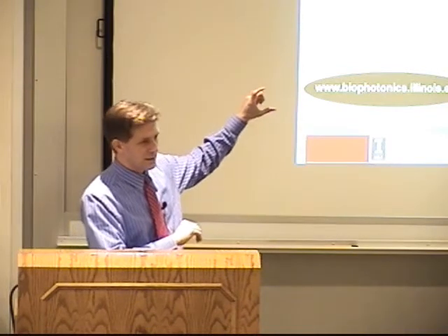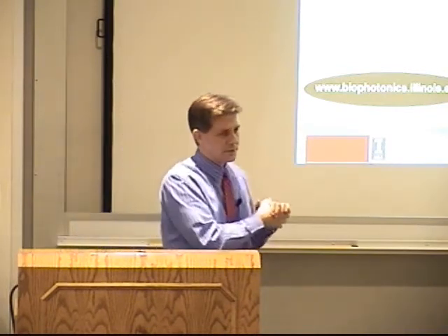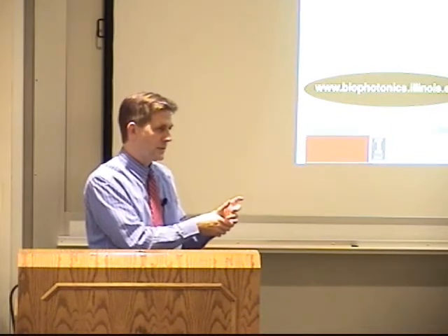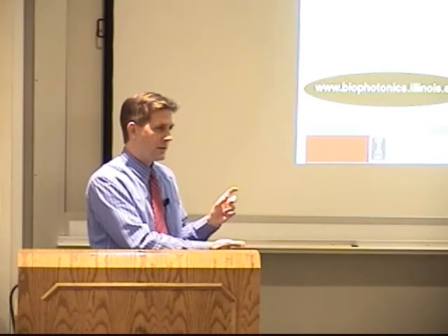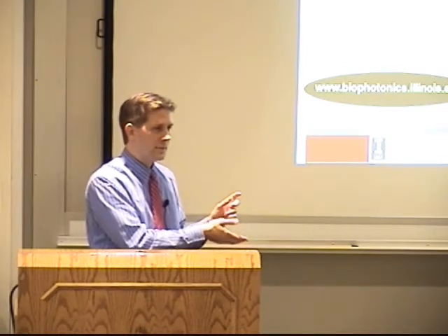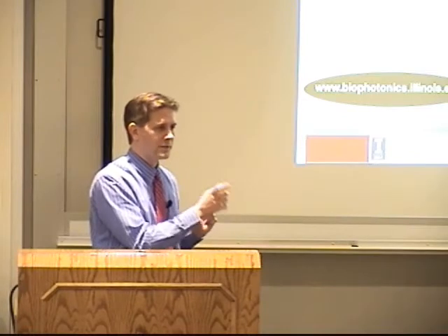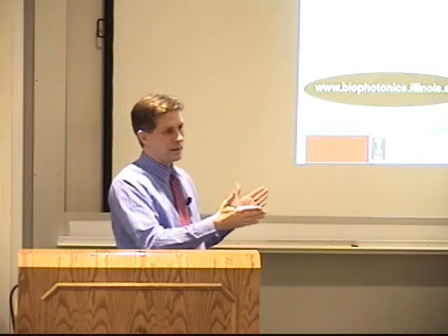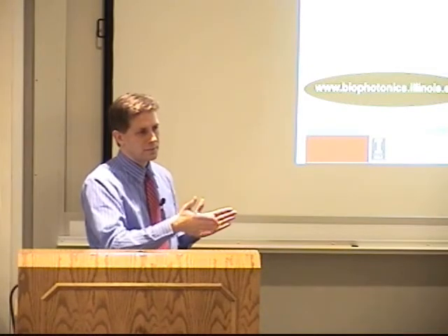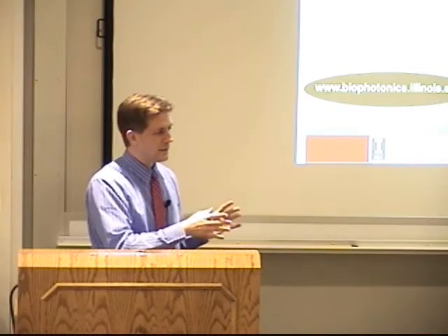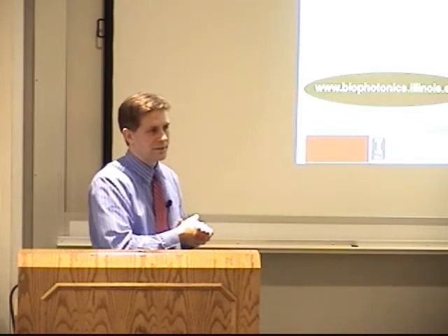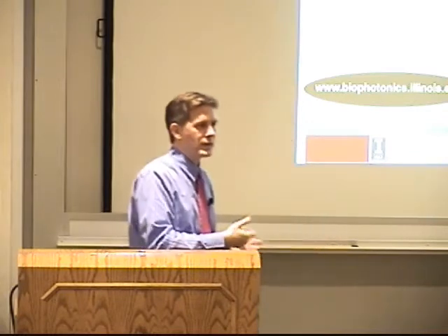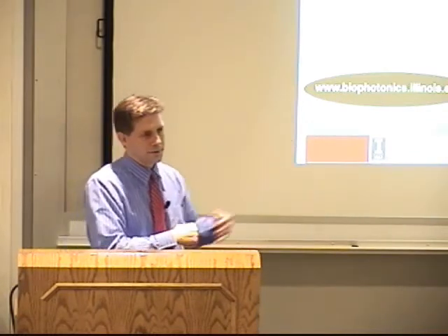Each one of those depth scans, I should say, I didn't go into a lot of the scanning techniques for OCT, but one method is to capture a spectrum of data coming from that depth. We have to do an inverse FFT. So that is the process, the bottleneck that has to be done on each A scan. And then that will allow us to look at the intensity profile in depth. That then is assigned or put into an array that will represent that image. There's a lot of other processing, dispersion compensation, that can be done. On top of that would be your classification.